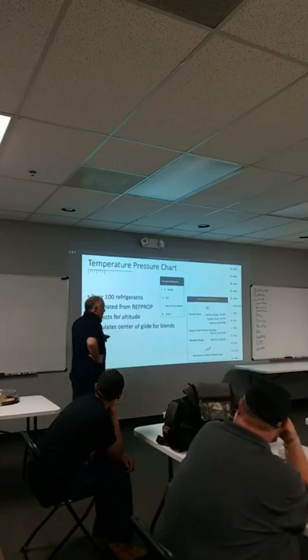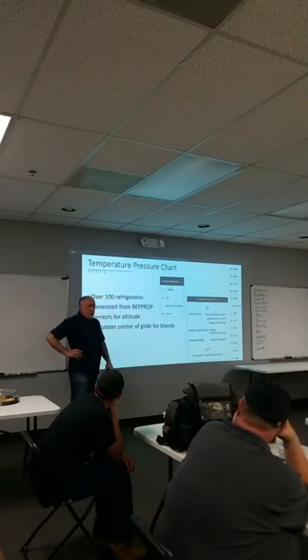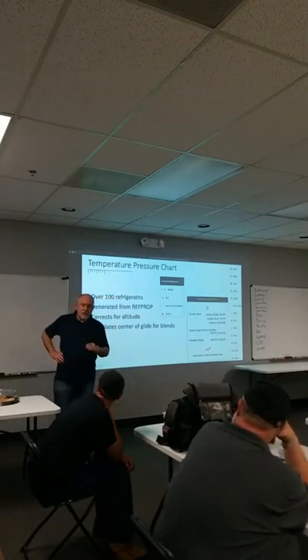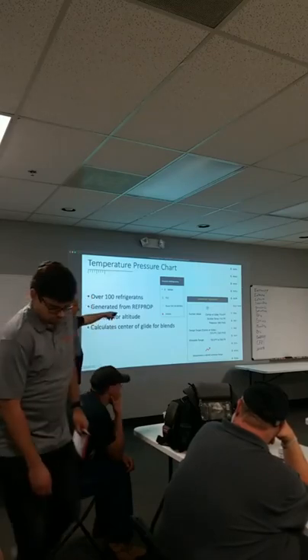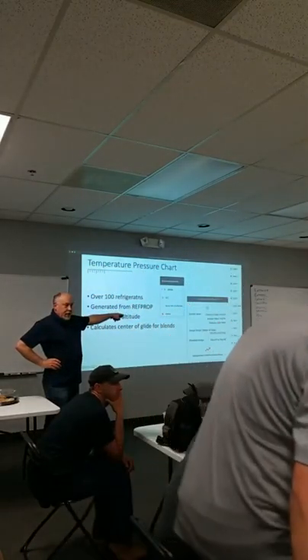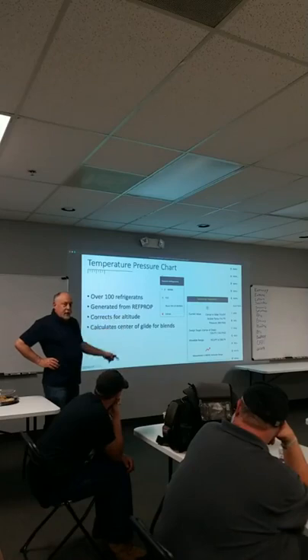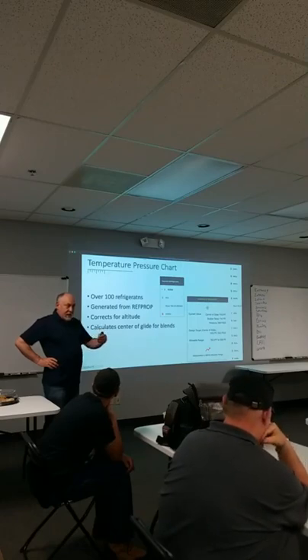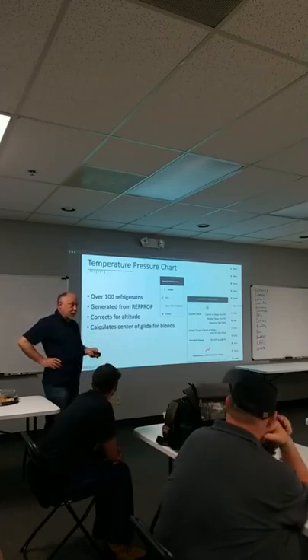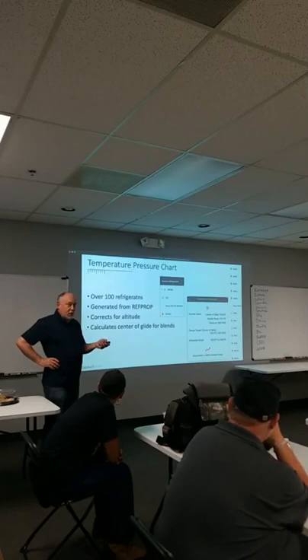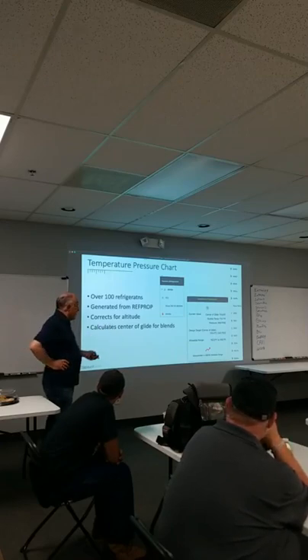So with Measurequick, because we're calculating the target pressure of the machine, we have to calculate the center of the glide. So if you're comparing your digital gauges, what you're gonna see is Testo and Fieldpiece show dew point and bubble point on their gauges. We actually show the saturation temperature. So we're calculating what you need to know, but we still use dew point and bubble point for superheat and subcooling respectively.